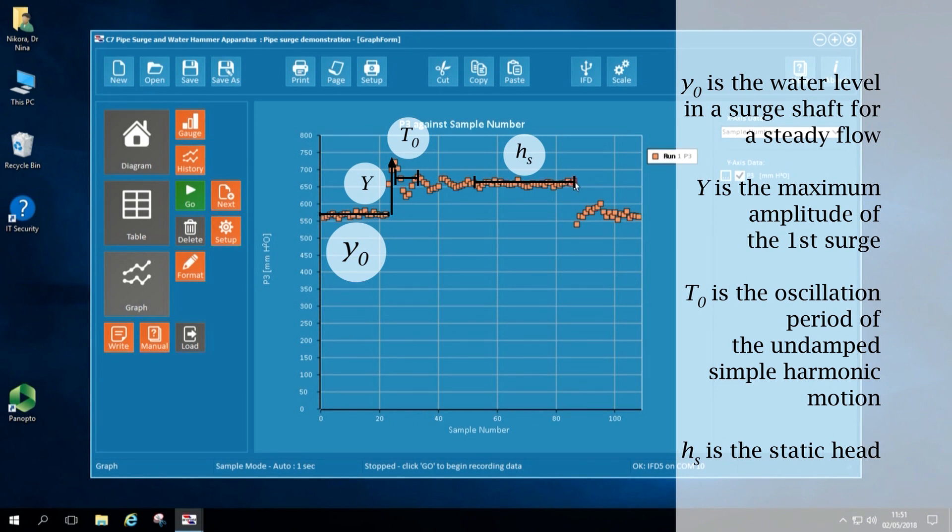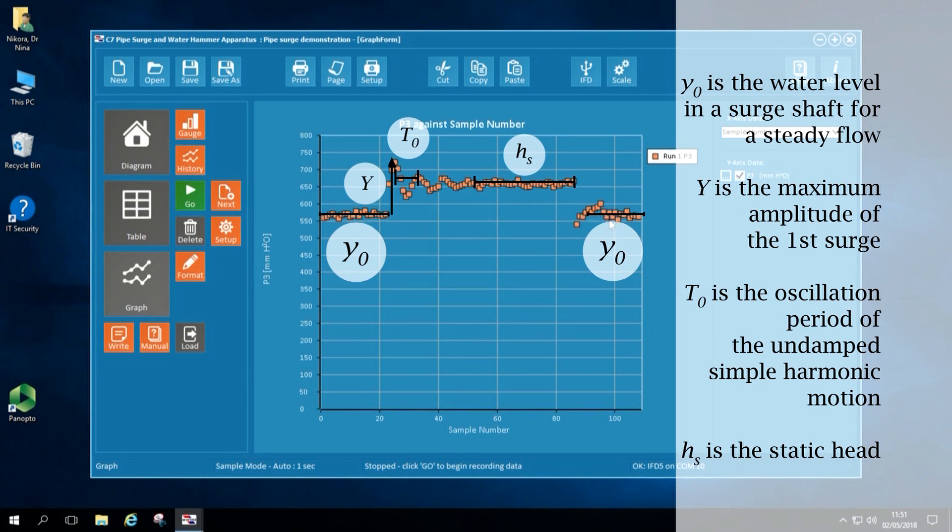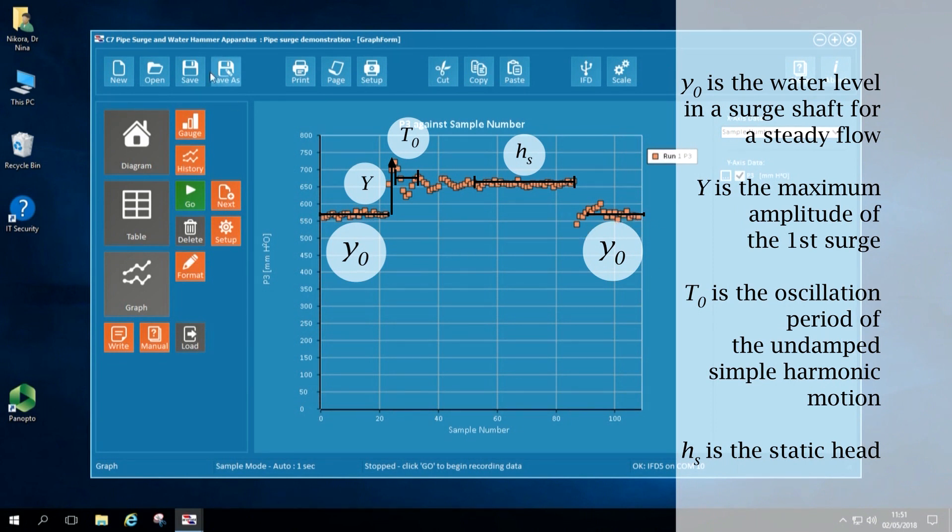After the valve was open again, I confirm that the water level in the surge tower returns to the initial water level in the surge tower. And indeed, the water level before the valve was closed is exactly the same as the stable water level in the surge tower after the valve was opened again.